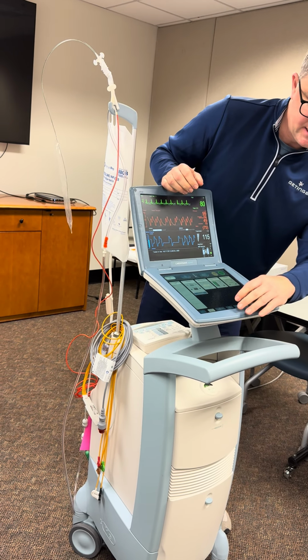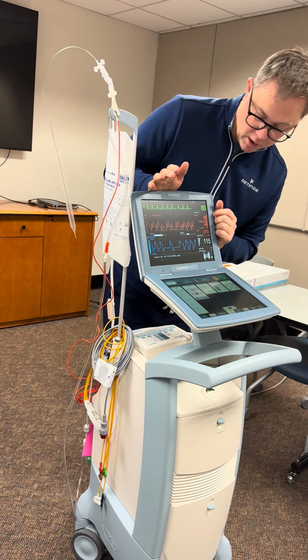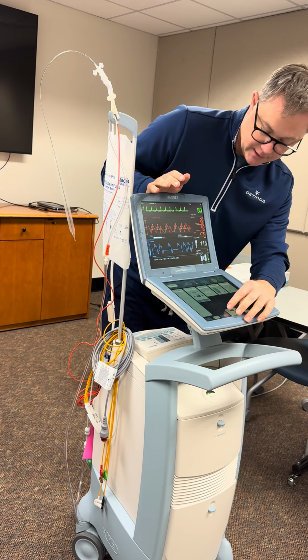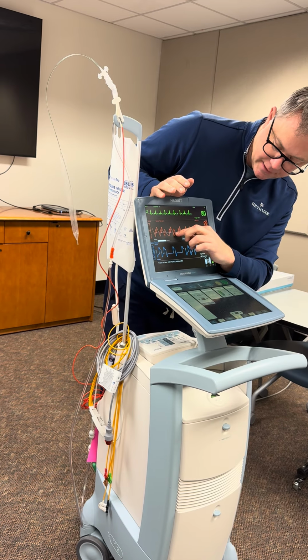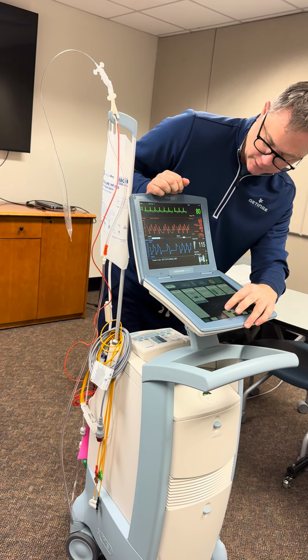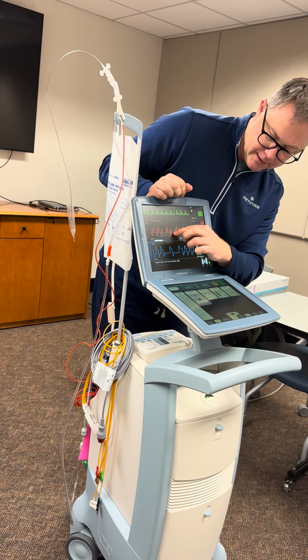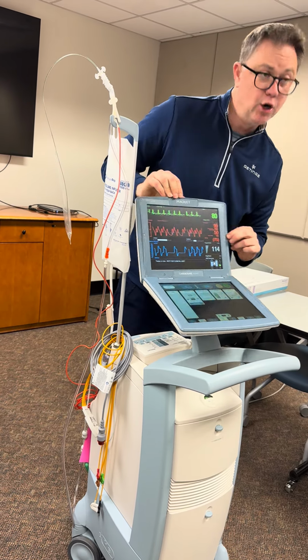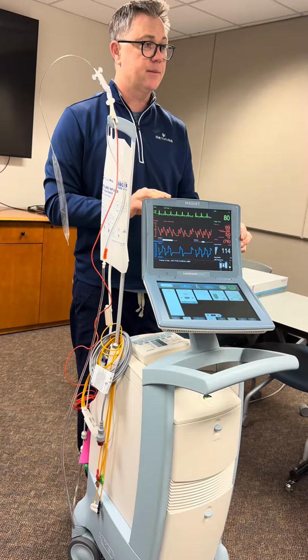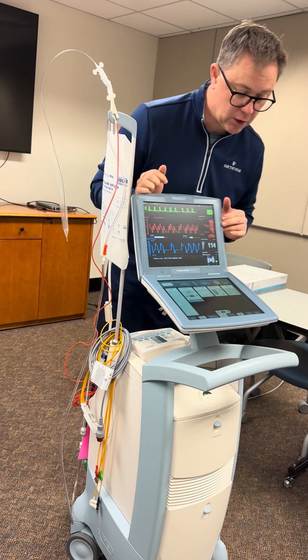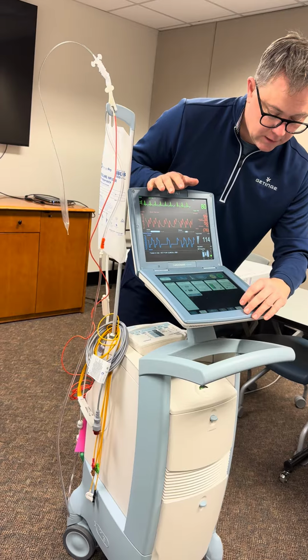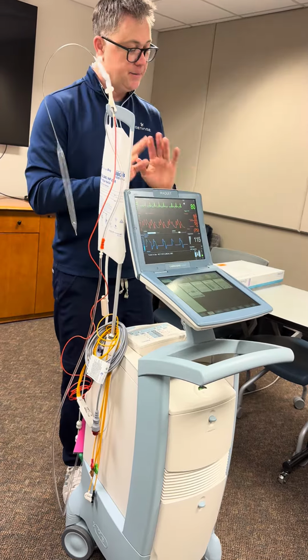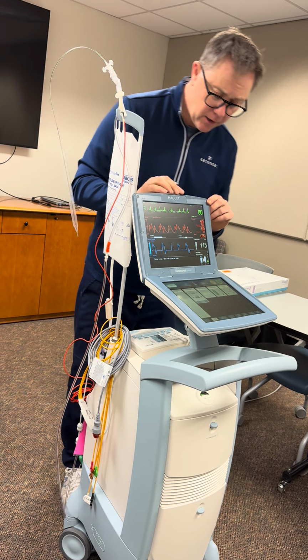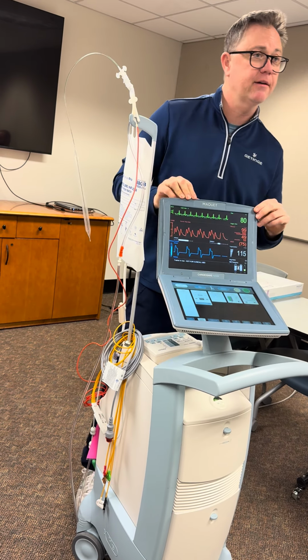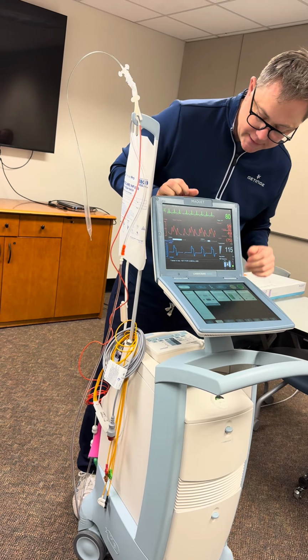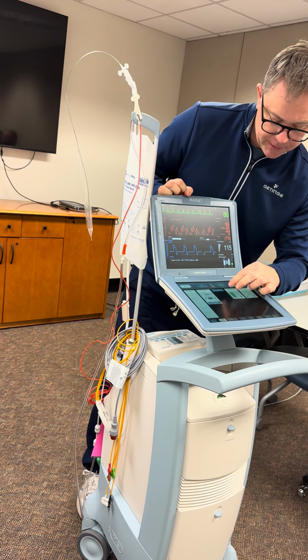So in the ICU, they'll do a timing check every so often, and they'll throw a reference line up like this, and they're gonna look for the dicrotic notch of the native arterial pressure waveform. I've gotta lower it down. Dicrotic notch is right here, and they'll push this reference line over, and that's where they wanna make sure that balloon's inflating. So it looks good, we're timing correctly. These pumps are very good at timing. You don't have to adjust them very much, but it's always good to do a timing check every once in a while and just make sure that we're timing correctly. So again, primary trigger, I'm gonna put it back into 1-to-1.